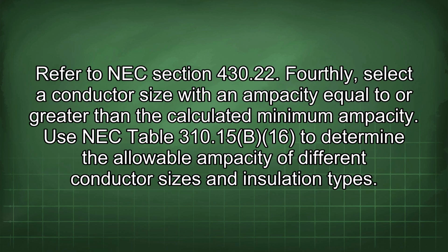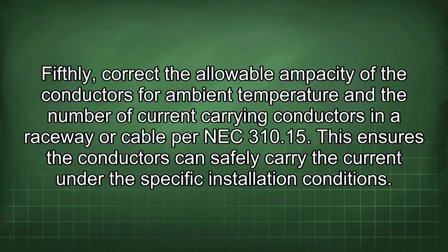Refer to NEC section 430.22. Fourthly, select a conductor size with an ampacity equal to or greater than the calculated minimum ampacity. Use NEC table 310.15(B)(16) to determine the allowable ampacity of different conductor sizes and insulation types. Fifthly, correct the allowable ampacity of the conductors for ambient temperature and the number of current carrying conductors in a raceway or cable per NEC 310.15. This ensures the conductors can safely carry the current under the specific installation conditions.